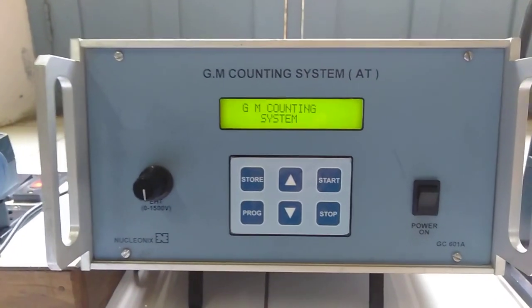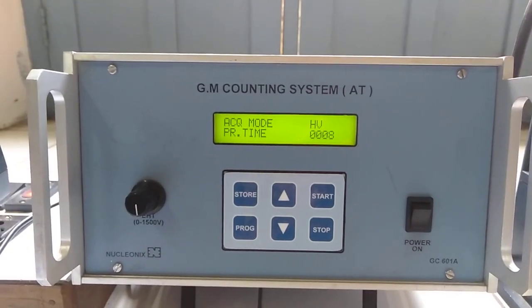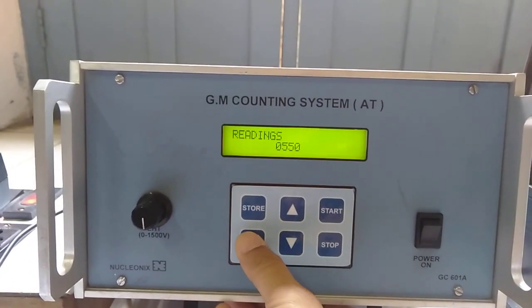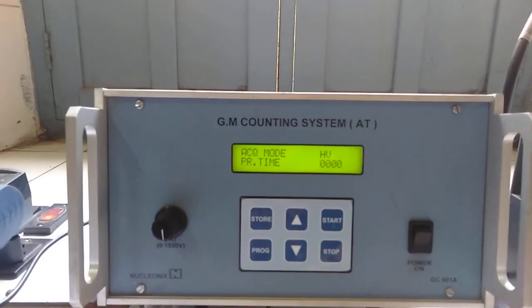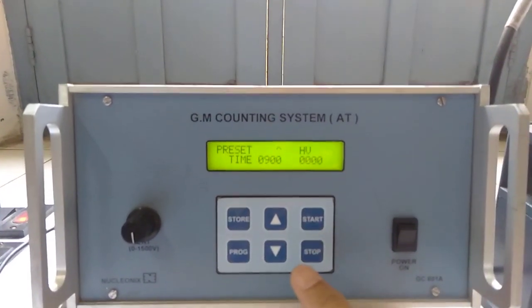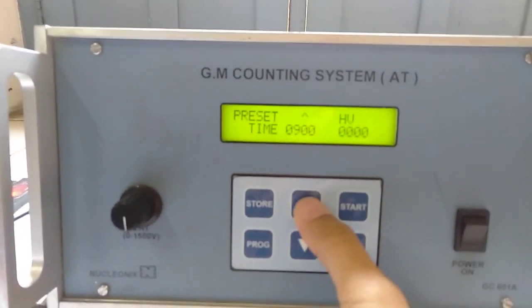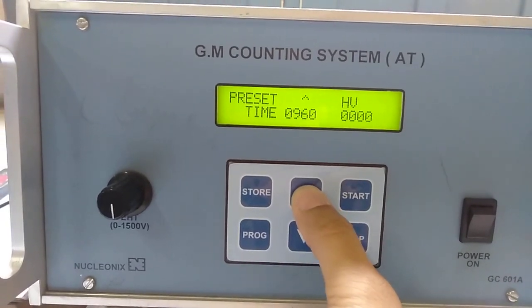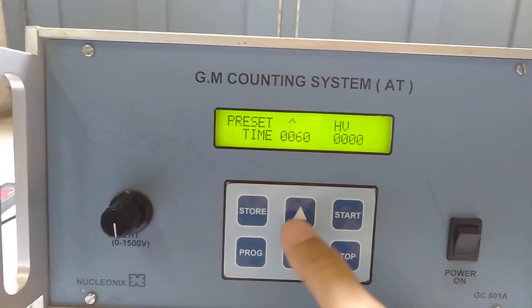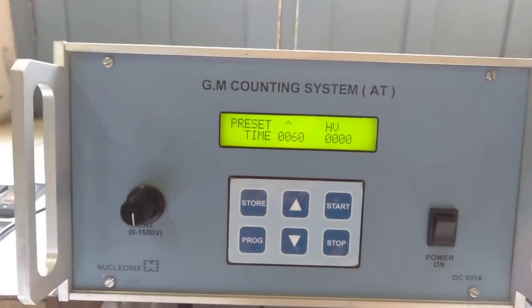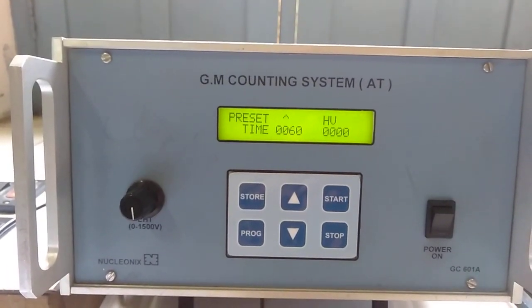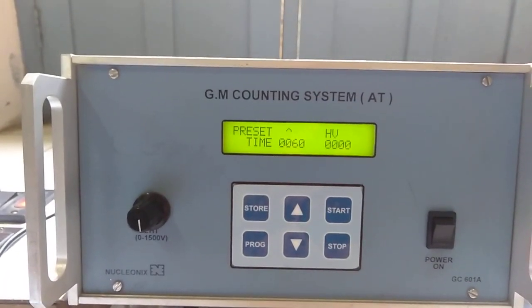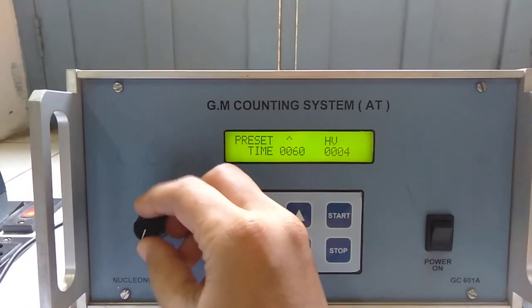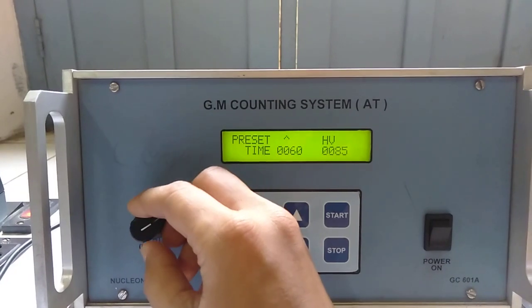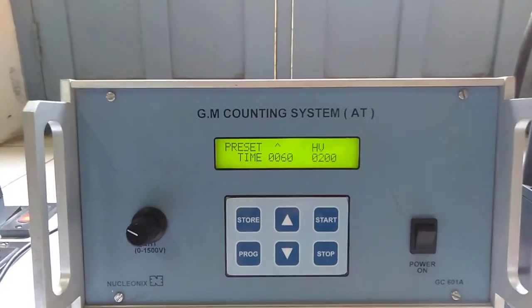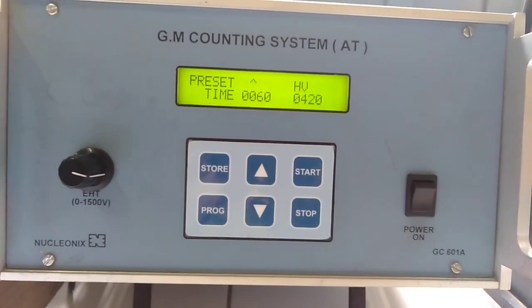You observe GM counting system, Nucleonix. Then press the program button. Set the preset time to 60 seconds. Move the cap and set this to 0. Set the high voltage of this GM counting system to its operating voltage. The operating voltage for this GM counting system is 420 volts. So using the high voltage knob, let me set the high voltage to 420 volts. High voltage has been set to 420 volts.